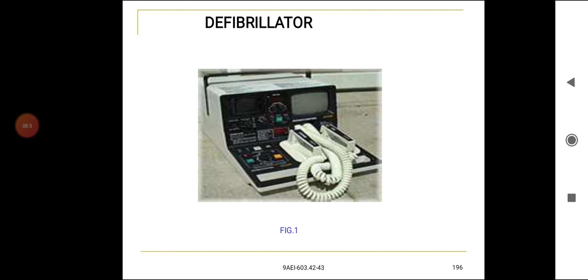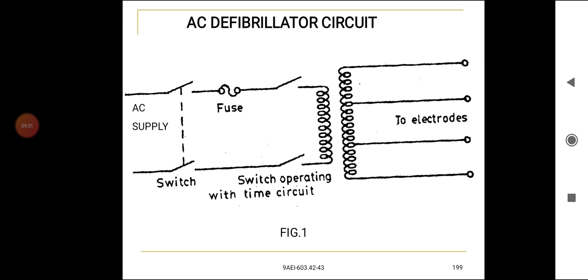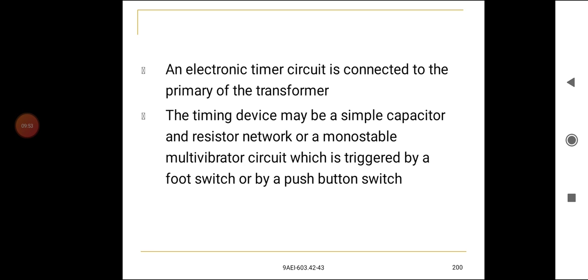AC defibrillator. The AC defibrillator is the earliest and simplest type of defibrillator. It consists of a step-up transformer with various tappings on the secondary side: AC supply, switch, fuse, switch operating with the timer circuit, to electrodes, and an electronic timer circuit connected to the primary of the transformer. The timing device may be a simple capacitor and resistor network or a monostable multivibrator circuit, triggered by a foot switch or push button switch.